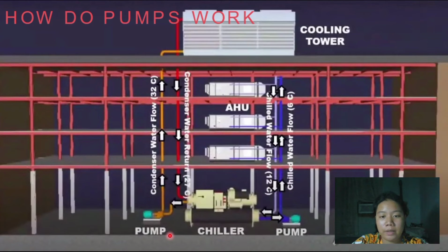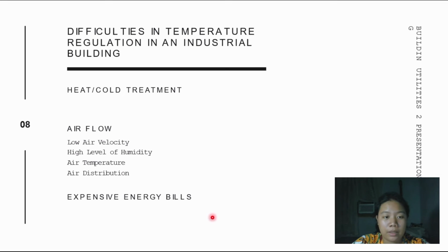The condenser water leaves the condenser of the chiller at around 32 degrees, as shown in the illustration, and the pump sends this up to the cooling tower. The system has been designed so that the condenser water leaving the cooling tower and re-entering the chiller condenser below must be around 27 degrees, in order for it to be able to pick up enough heat for its next cycle. Next, the difficulties in temperature regulation in an industrial building.